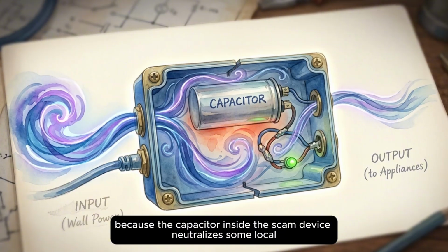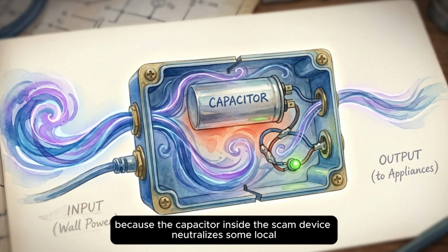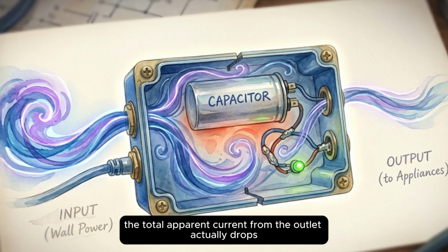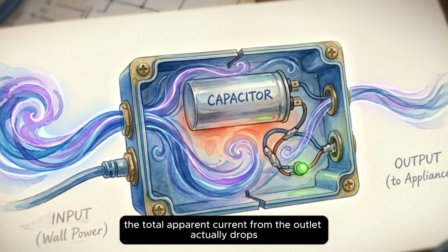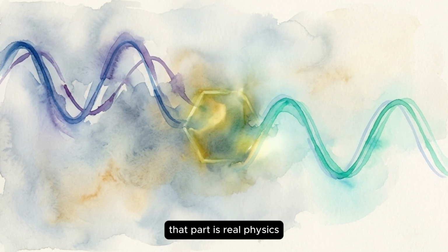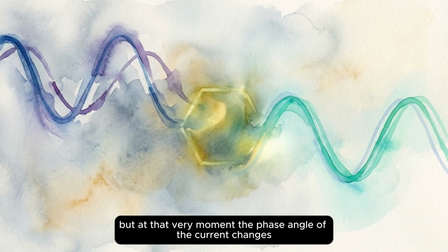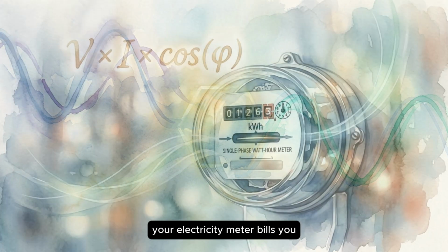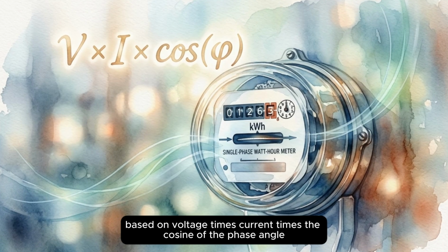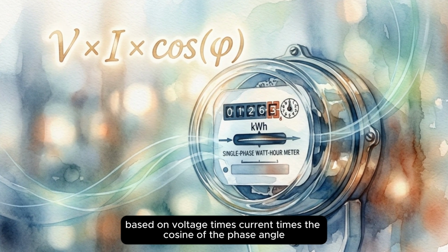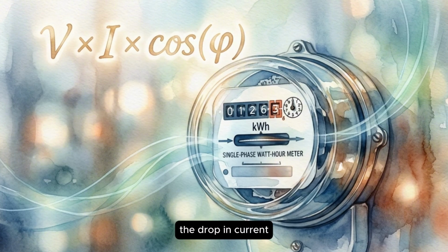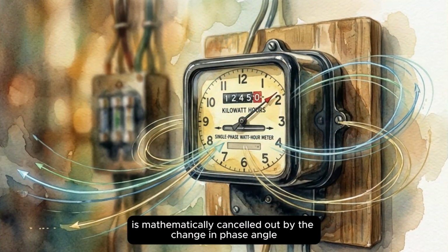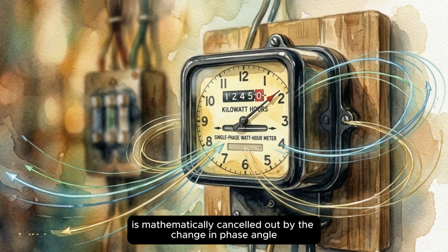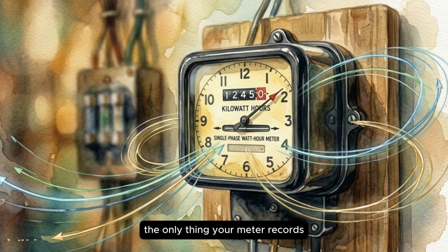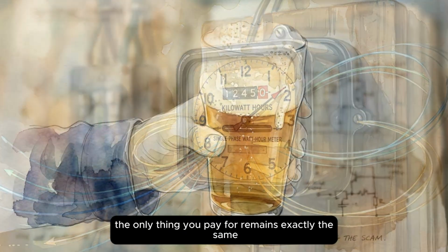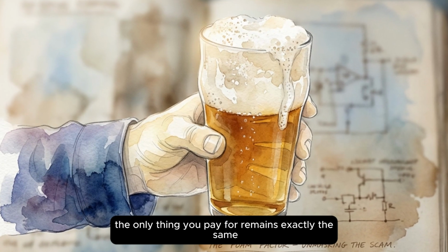Because the capacitor inside the scam device neutralizes some local reactive power, the total apparent current from the outlet actually drops. That part is real physics, but at that very moment, the phase angle of the current changes. Your electricity meter bills you based on voltage times current times the cosine of the phase angle. The drop in current is mathematically canceled out by the change in phase angle. The actual wattage consumed, the only thing your meter records, the only thing you pay for, remains exactly the same.